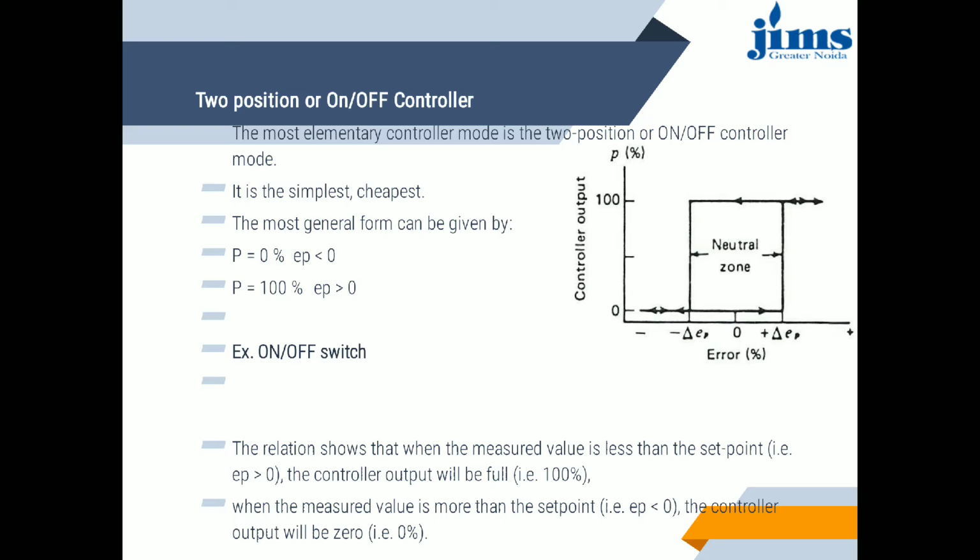With a decrease in dead zone, the number of on-off switchings of the controller increases, and therefore the useful life of the component decreases. Hence the dead band should be designed to prevent oscillations in the on-off controller. The two position control mode is used in room air conditioners, heaters, and liquid level control in large volume tanks.